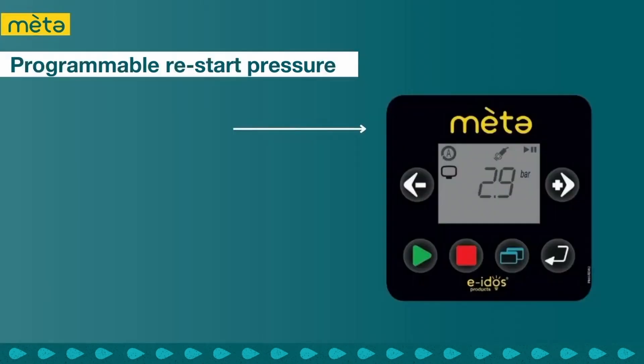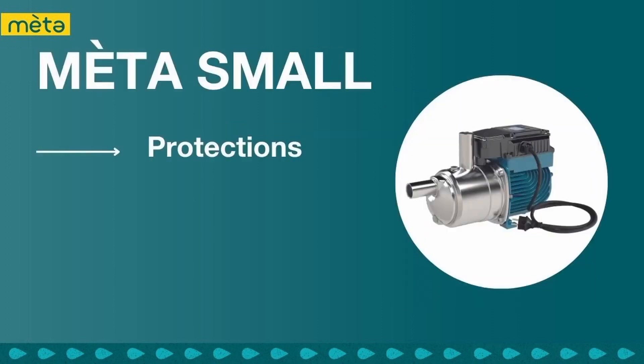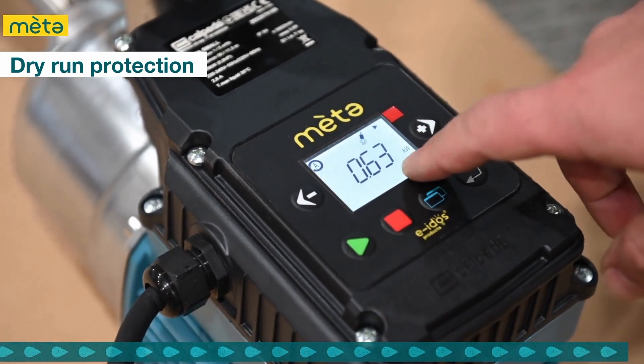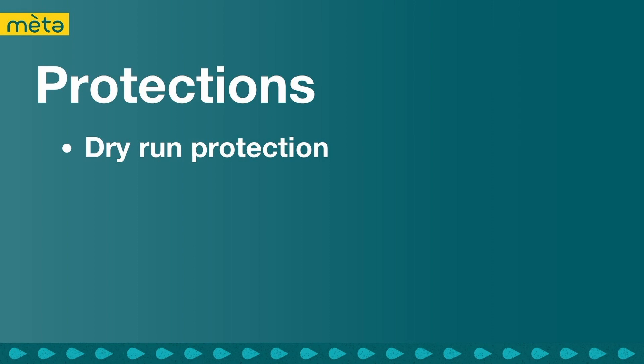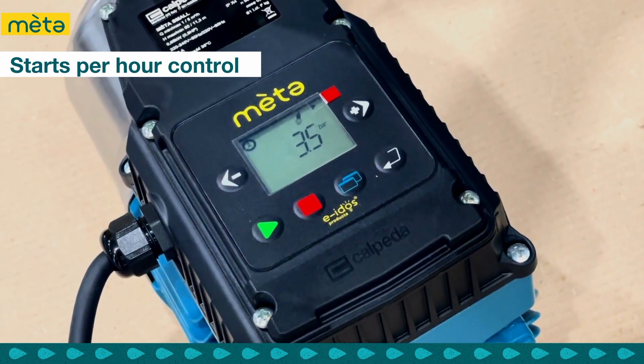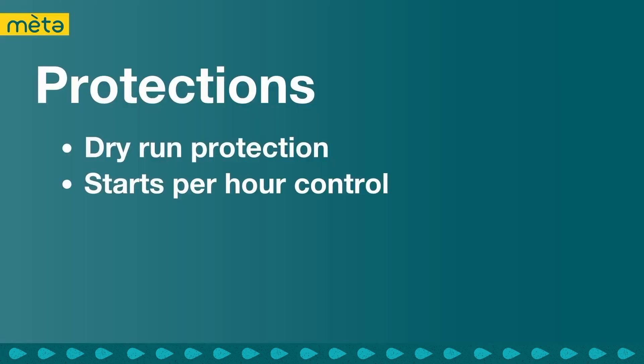With programmable restart pressure, the operator can set a specific pressure at which the pump will automatically restart after it has been turned off. Calpeda pumps are designed and manufactured with built-in protections, ensuring their longevity and durability over time. The Dry Run Protection System detects the presence of air in the pump casing and shuts off the pump if it detects air, preventing damage from overheating. The Starts Per Hour Control System monitors the number of starts per hour and shuts off if it exceeds the threshold, preventing wear and tear on the motor and other components.